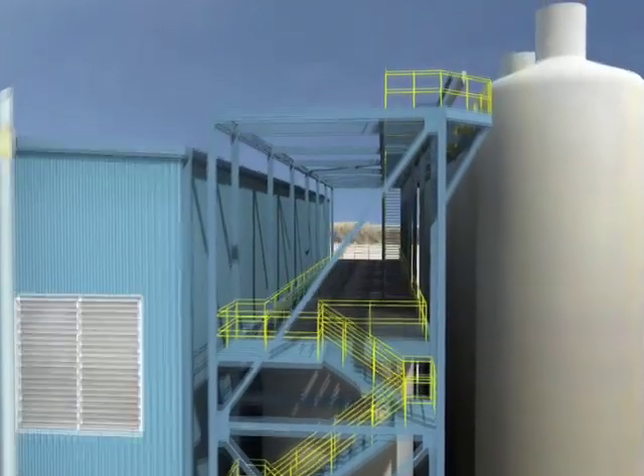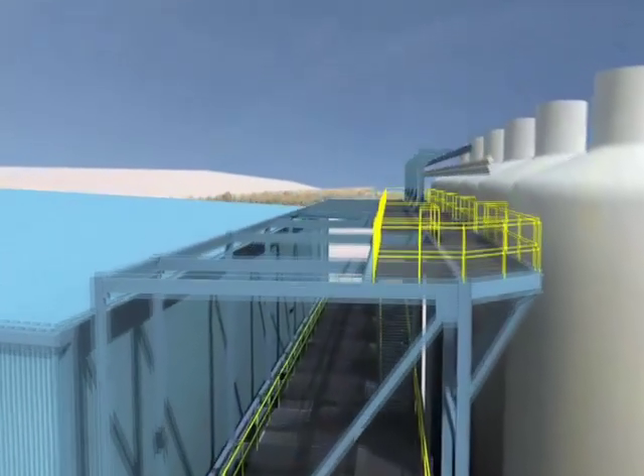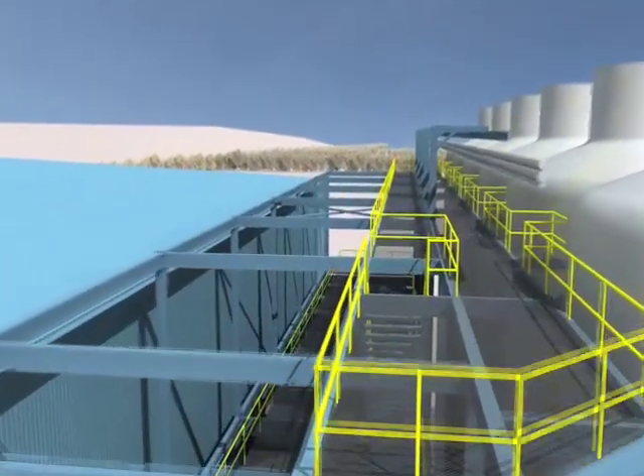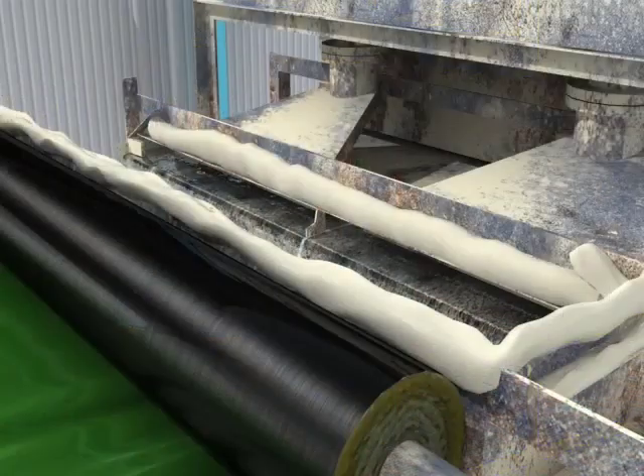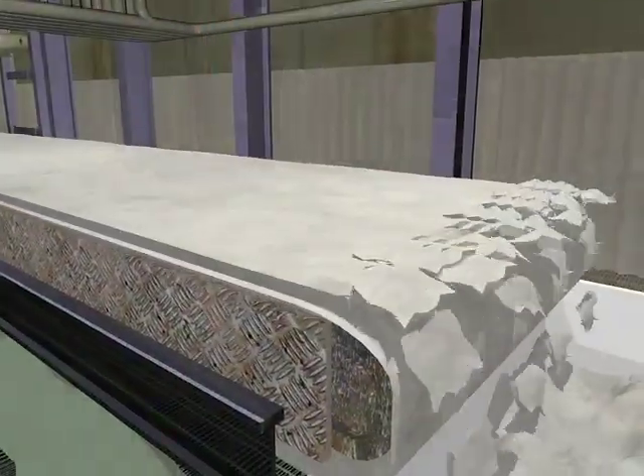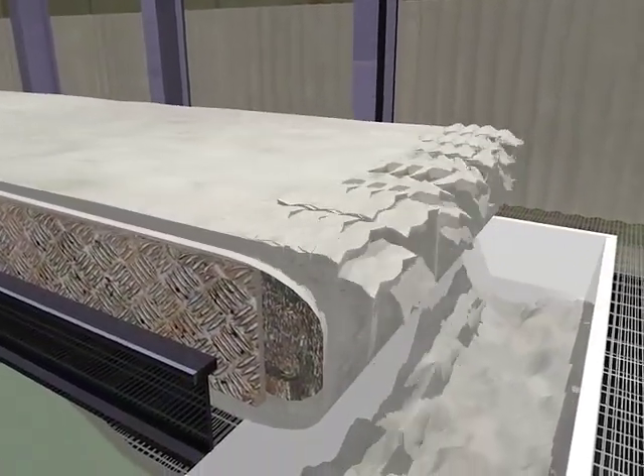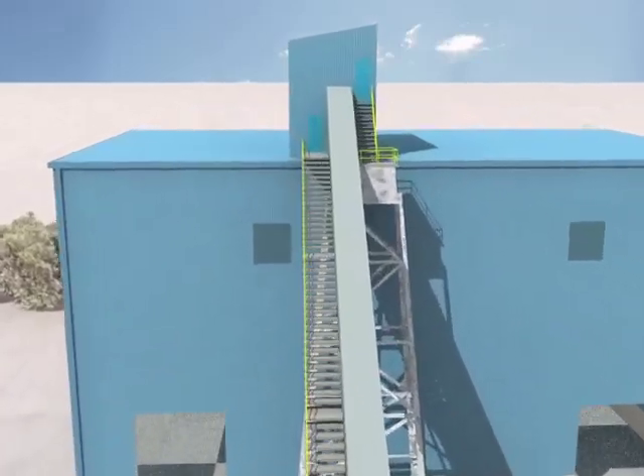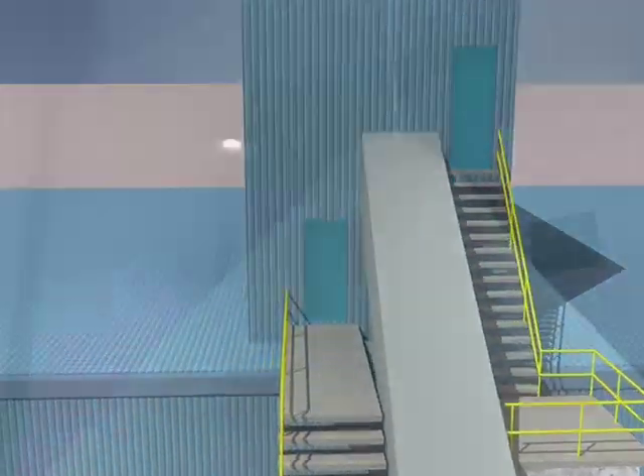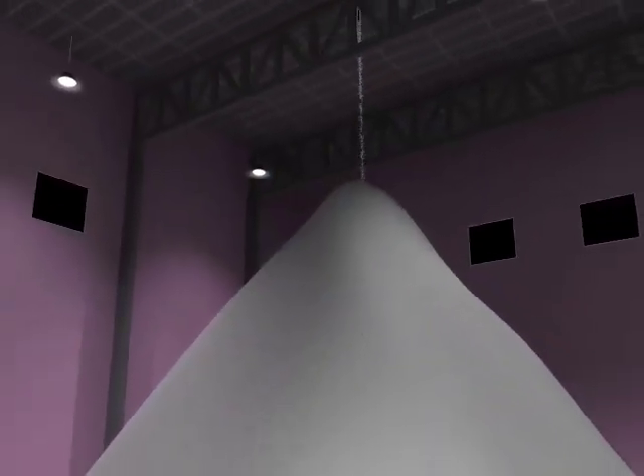The slurry leaving the scrubbers is thickened and pumped through a forced oxidation gypsum, or FOG, system. Oxygen is then added, changing it into gypsum, which is dried, treated, and sent to a gypsum manufacturer to make wallboard. First Energy recycles about 500,000 tons of gypsum each year, enough to manufacture wallboard for 70,000 new homes.